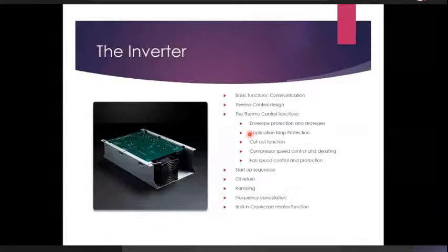Then for paucity of time, I would say this is a simpler self-explanatory slide, which does most of the part that an inverter is expected to do, which is compressor speed control, derating, cutoff function, and application map protection, and also offers fan speed control. There is another thing called crankcase heater function. So when the compressor is off for a long duration during winter months, we need to be able to keep the compressor warmer than the rest of the system, so that all the refrigerant doesn't migrate into the compressor. If that happens and then the compressor is started after the winter months are over, then there is a possibility that the entire refrigerant will be taken out, and that can cause compressor failure. So this function is also integrated.